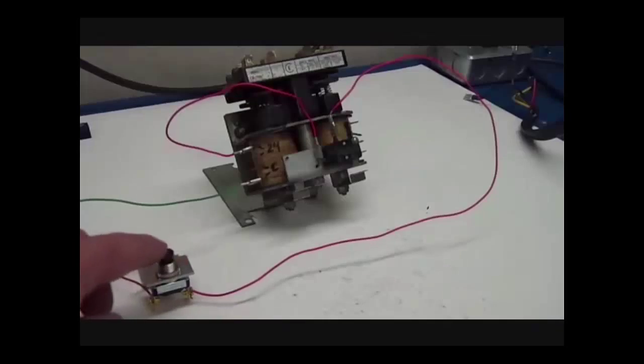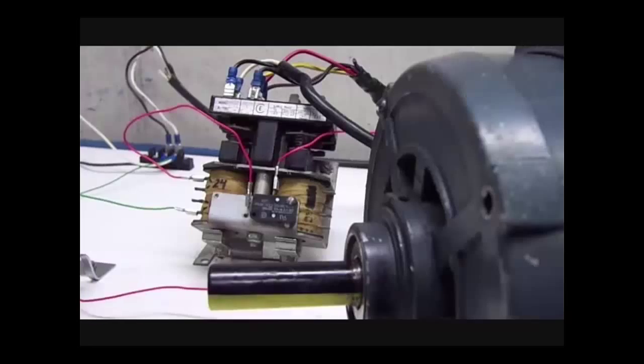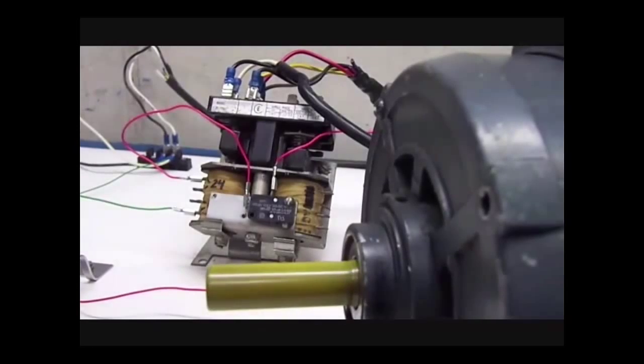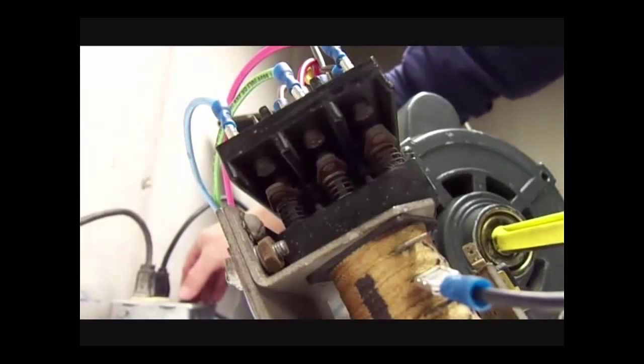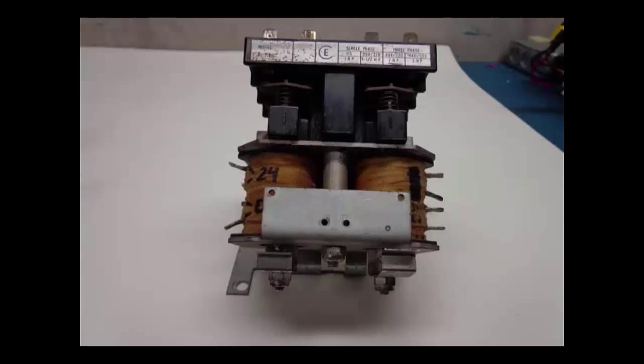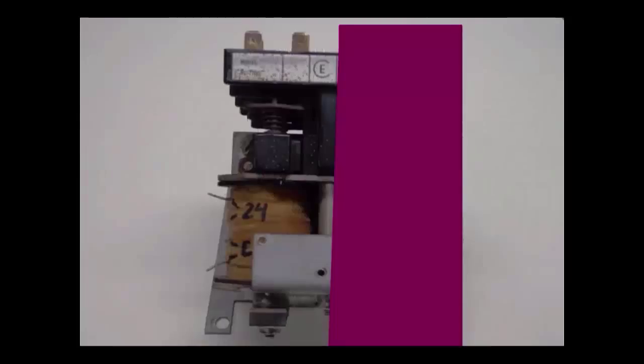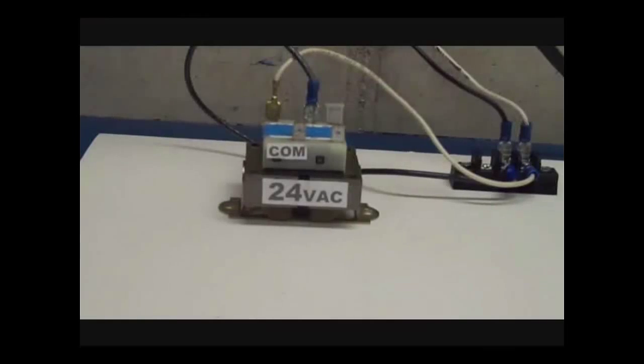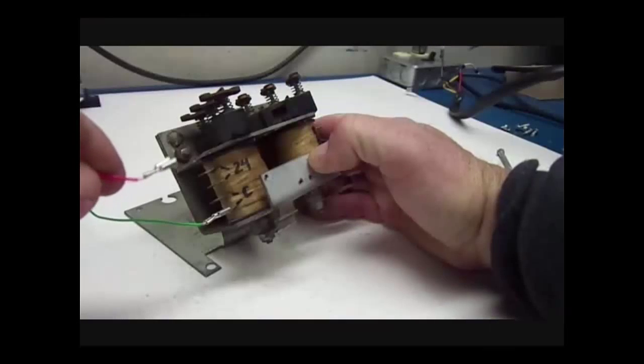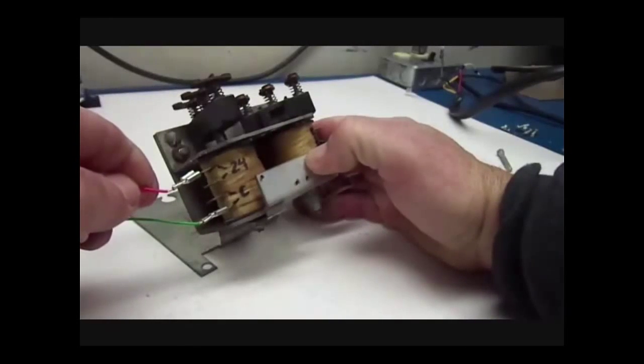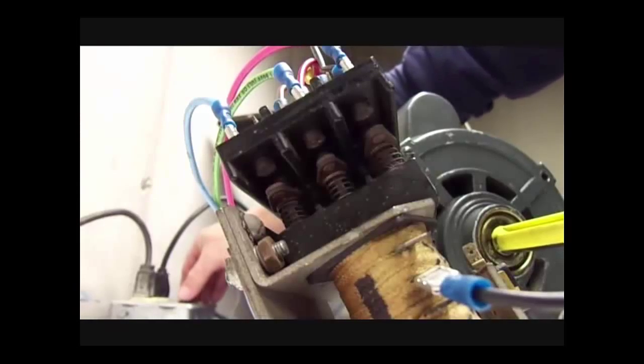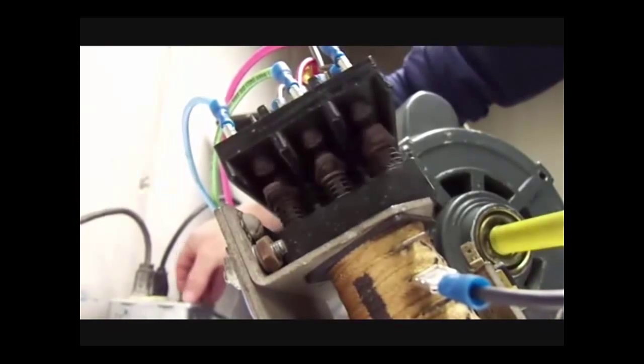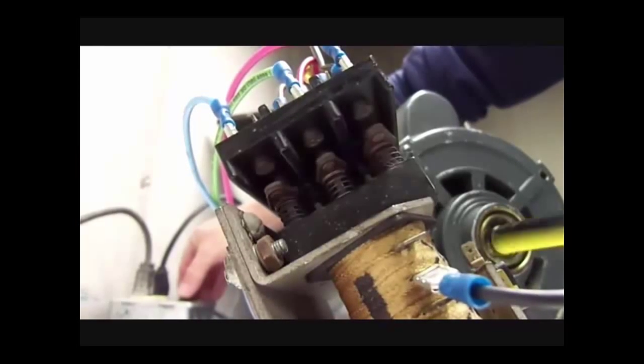This is an old school reversing contactor, so it's basically two identical contactors interlocked together on a single frame. One side is to run the motor clockwise and the other side is for counterclockwise. But forget about the one on the right for now. Let's just pretend we have a single contactor. It has a 24 volt AC coil, like most of them do, which pushes or pulls together the high voltage contacts, allowing current to flow to the motor.